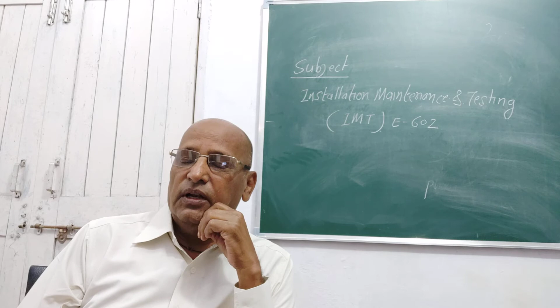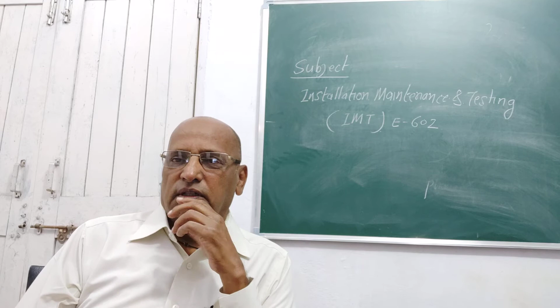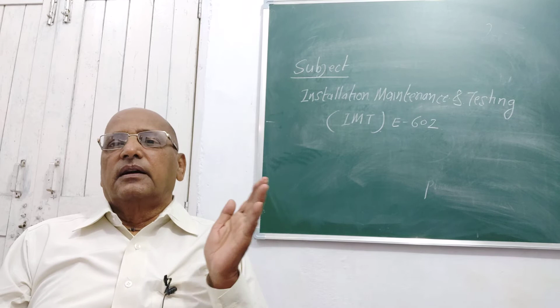Many times equipment is provided with a number of accessories. For example, a transformer has a conservator tank, radiators, and other components. For shifting purposes, we often disconnect the radiators if possible, and remove the conservator tank from the nut-bolt portion. Whatever detachable accessories are present on the heavy equipment can be detached, and when it is installed at the commissioning site, all these accessories are fitted back on, so that loading, unloading and transportation become simple.